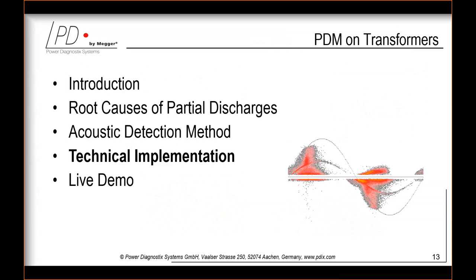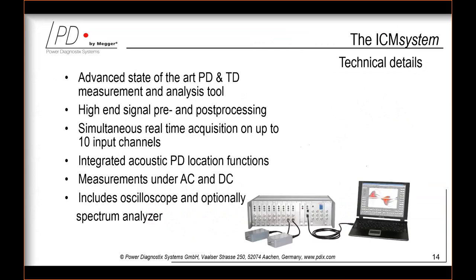For technical implementation, we use the ICM system — our advanced state-of-the-art PD and loss factor measurement and analysis tool. It has high-end signal pre- and post-processing, can simultaneously acquire up to 10 input channels in real time, has integrated acoustic PD location functions, can perform measurements on AC and DC voltages, and includes an oscilloscope and optionally a spectrum analyzer.